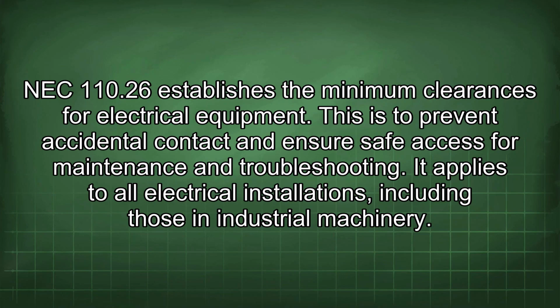NEC 110.26 establishes the minimum clearances for electrical equipment. This is to prevent accidental contact and ensure safe access for maintenance and troubleshooting. It applies to all electrical installations, including those in industrial machinery.